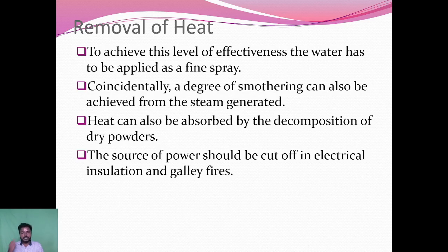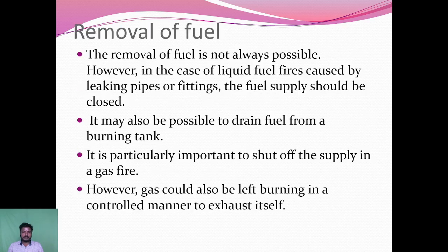A degree of smothering can also be achieved from the steam generated. Heat can also be absorbed from the decomposition of dry powder. The sources of power should be cut off in electrical installations and galley fires. The removal of fuel is not always possible. However, in the case of liquid fuels, such as fires caused by leaking pipes or fittings, the fuel supply should be closed.